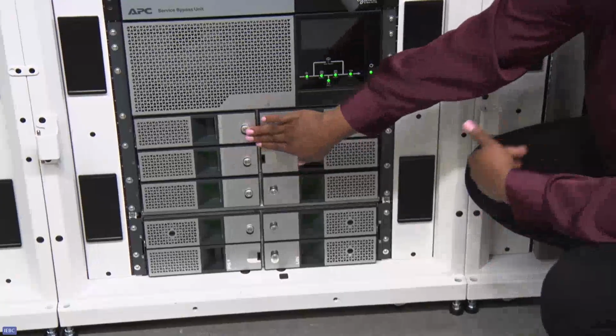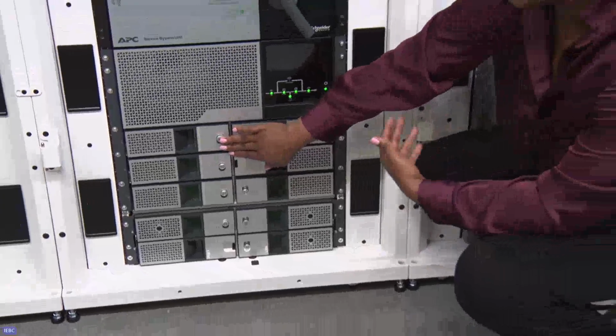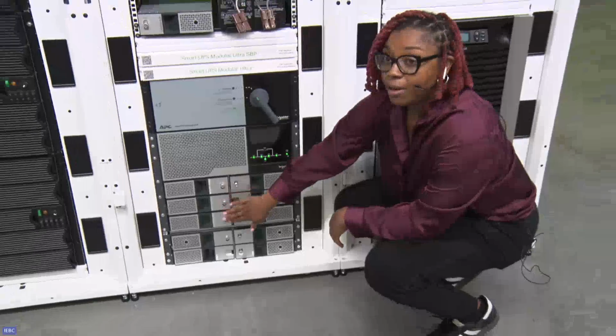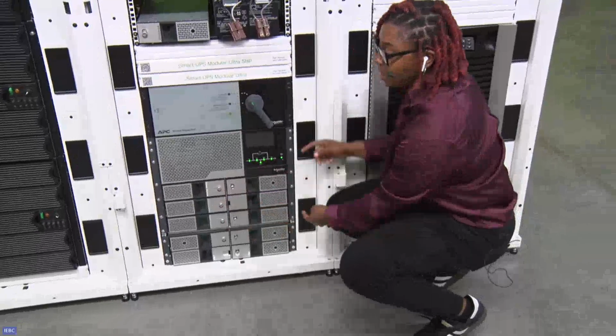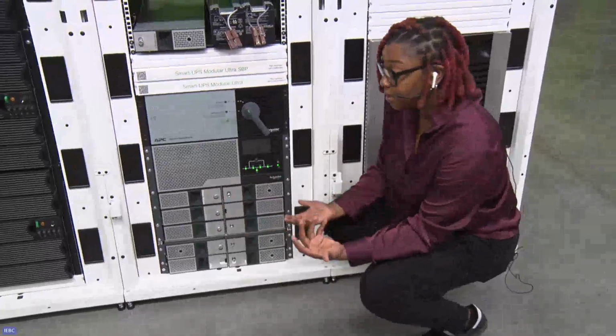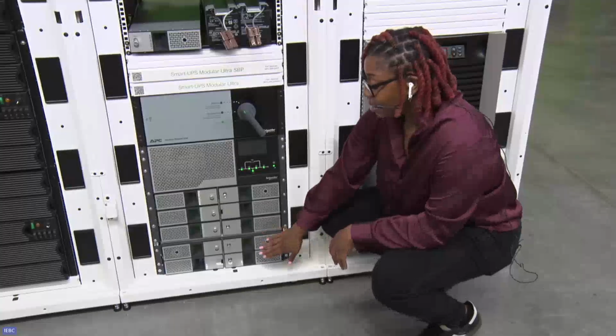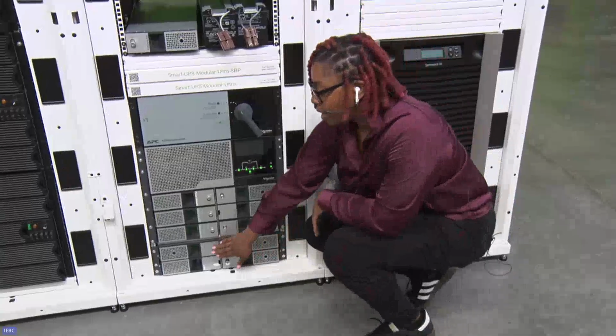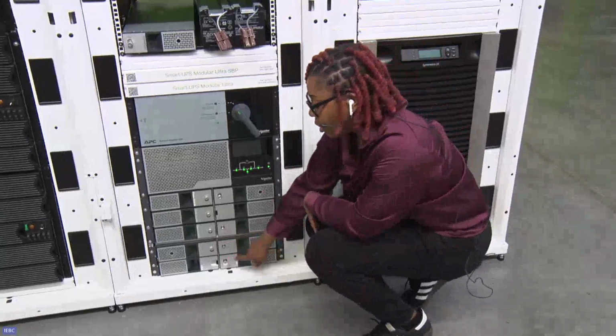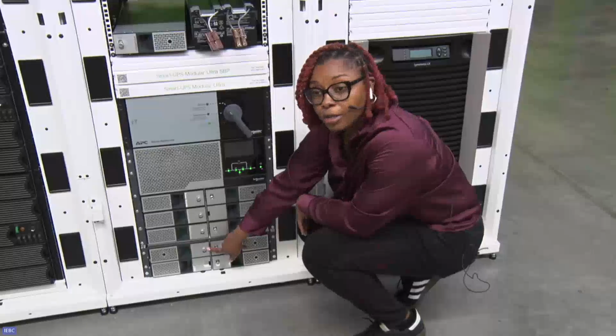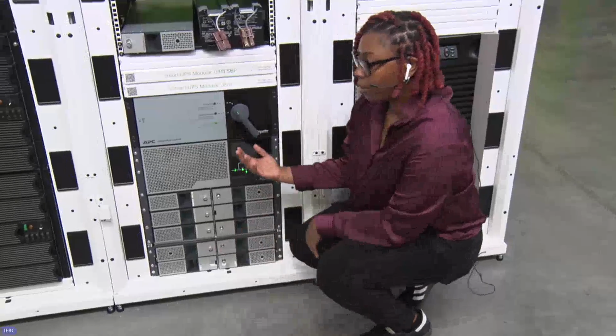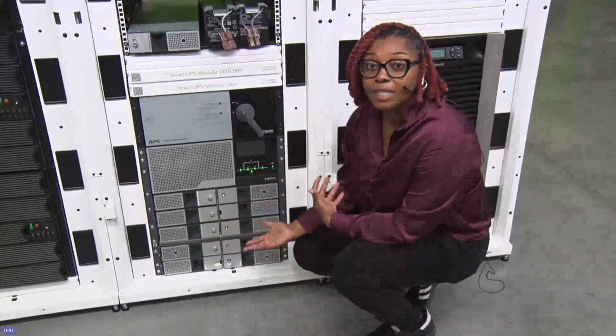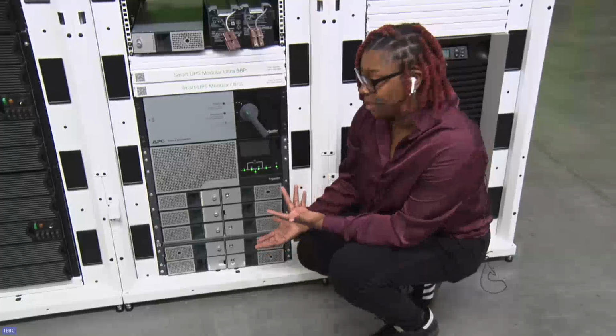These are 5 kW power modules, and they are power factor corrected. You can go 5, 10, 15 kW total in just 9U spaces, which is pretty impressive. This maxes out at 20 kW—you can add this additional shelf here and get another power module in, so you can either do 20 kW max, or 15 kW N+1 for redundancy.